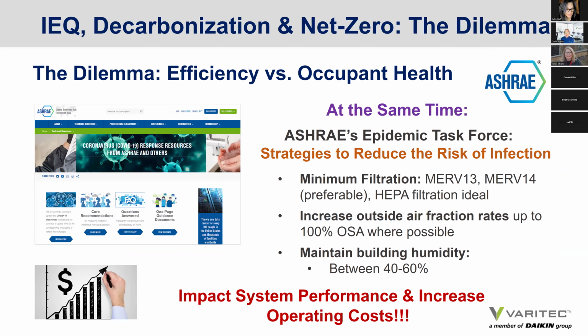Well, on the other side of the coin, going back to air quality, how do we improve building air quality? ASHRAE's Epidemic Task Force gave tremendous guidelines for reducing the risk of infection, but all of them mean adaptations of HVAC systems that add energy cost and the operational cost of a building by increasing minimum filtration levels to MERV 13, ideally MERV 14, if not, perhaps HEPA filtration, which is unrealistic for most commercial applications.